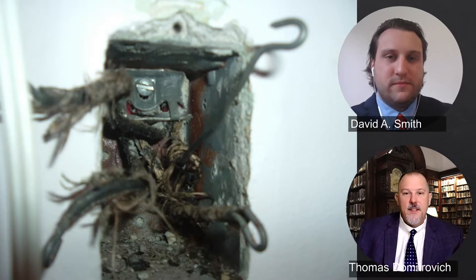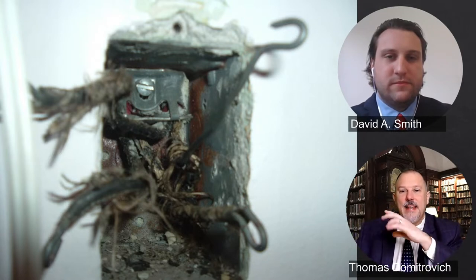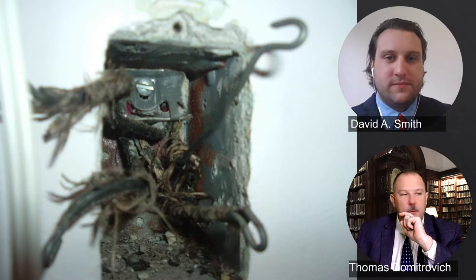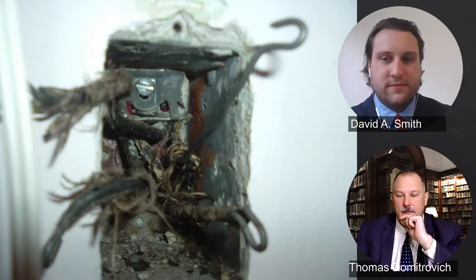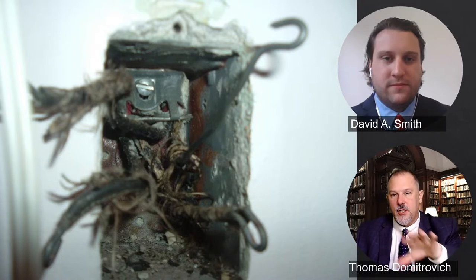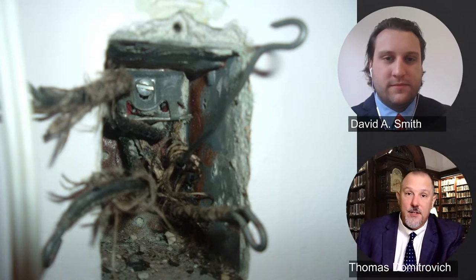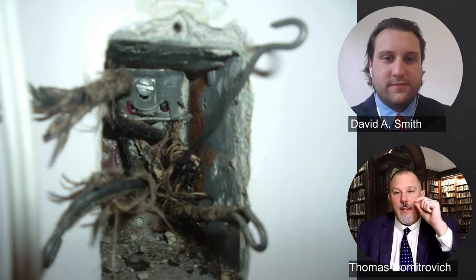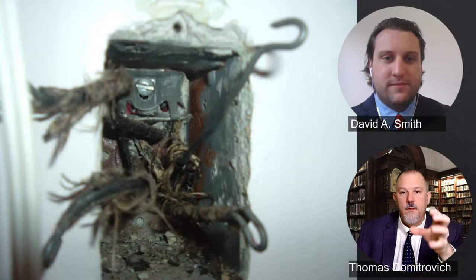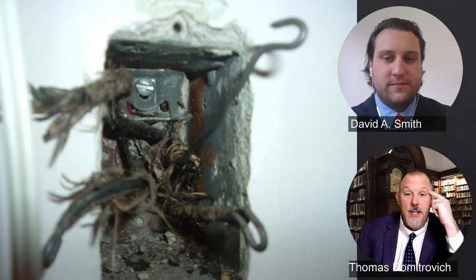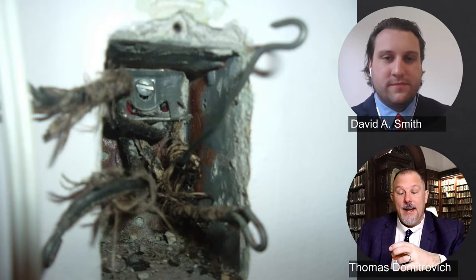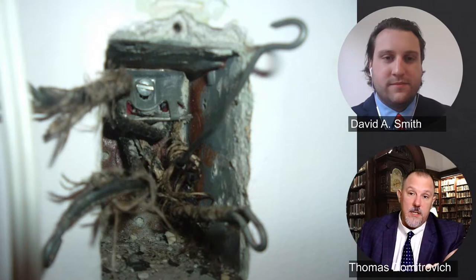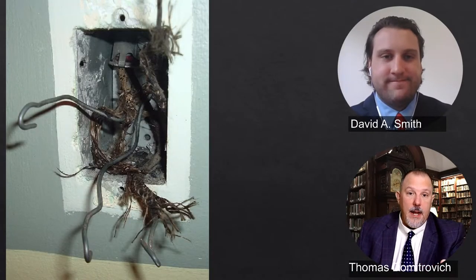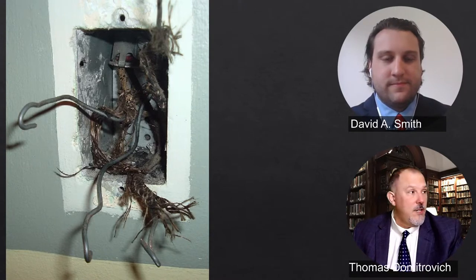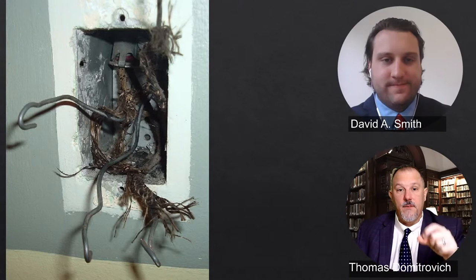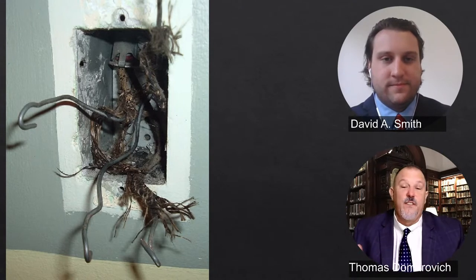This was one of them. This was a picture on an outside wall. You can just barely see the brick in the back, through the back of the box. It's a metal box and you can see rust on that box. You could tell the age of the wiring because the insulation was so brittle. When we removed it, I forget, it was Bruce Terhorst who was the electrician, he removed the receptacle and I could not believe the insulation just, there was no insulation on a couple of these wires. And the ones that did have insulation, like you can just barely see it on that one wire coming out to the pop top in the back there, the insulation, he moved it and it just fell off.